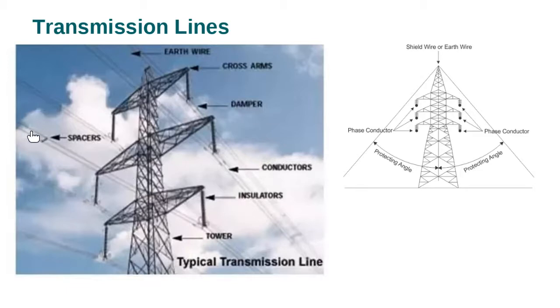Also, on each phase we have 2 transmission lines, or cables, separated by spacers. These 2 lines, separated by a spacer, are called bundle conductors—so this is a 2-bundle conductor, 3-phase, 2-circuit line. Instead of having one big cable per phase, we have two smaller cables on the same phase. So we have 6 cables total, but only 3 phases, since each phase has 2 cables.